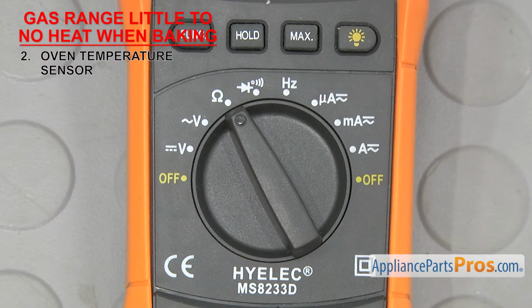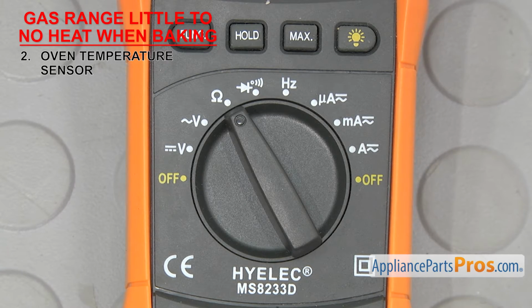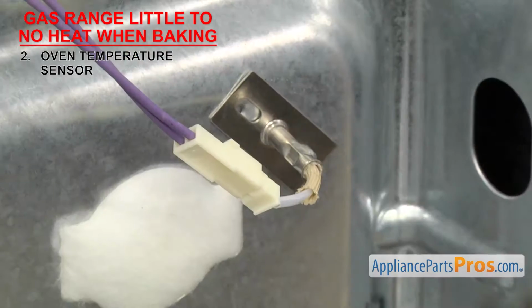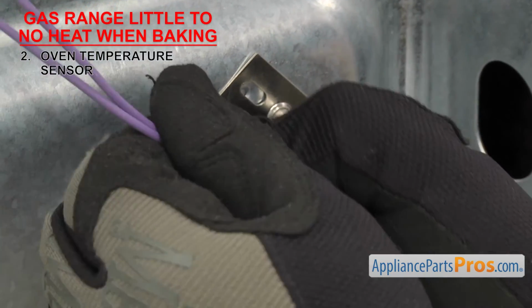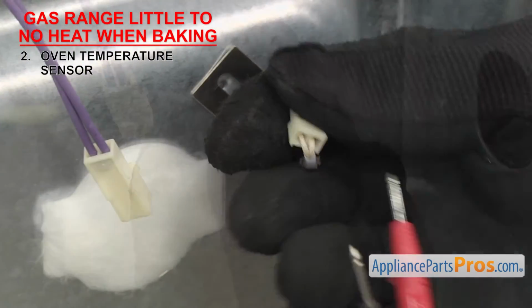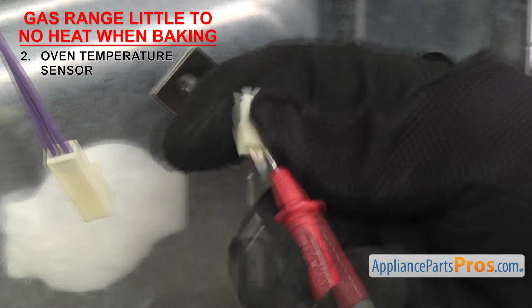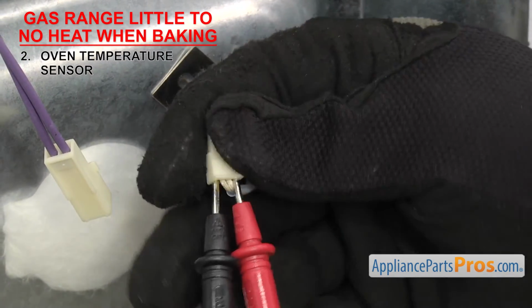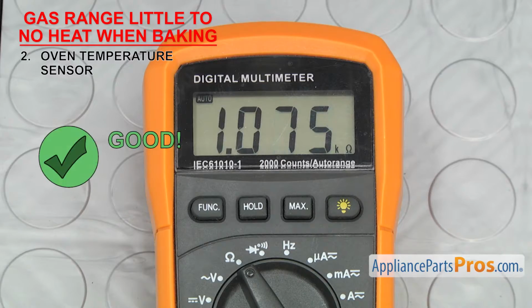So set your meter to ohms. Our meter automatically detects whatever ohms are coming in, but you may need to set your meter to read the proper ohm level. Once you have access to the sensor, remove the wires and touch a test probe to each terminal. If the ohms reading is way off, or you don't get a reading at all, it'll have to be replaced.